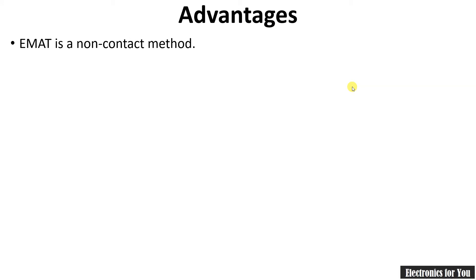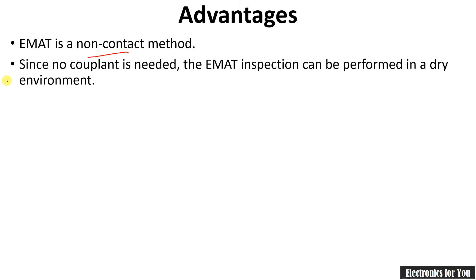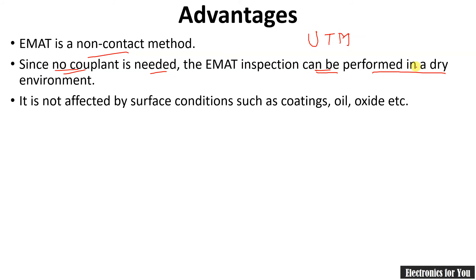Now let us see the advantages of EMAT. EMAT is a non-contact method — no couplant is required. In ultrasonic thickness measurement, a couplant is generally required, but in the case of EMAT there is no need for a couplant, so you can measure thickness in a dry environment.